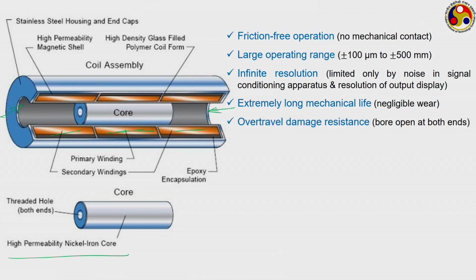Overtravel damage resistance. As I have mentioned here, both ends are open, and therefore if the core is made to travel more than it is supposed to, no damage will be done. It can be protected, and as the core pops out of the system there will of course be no voltage induction, and hence the device will stop working for that instant, and then you can easily get the core back into its normal position and the device will be back.